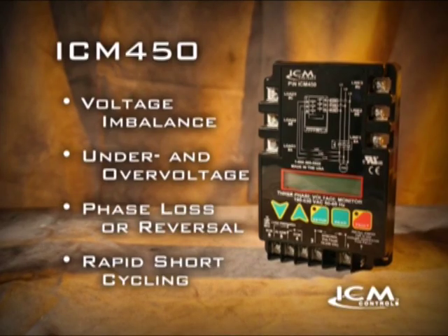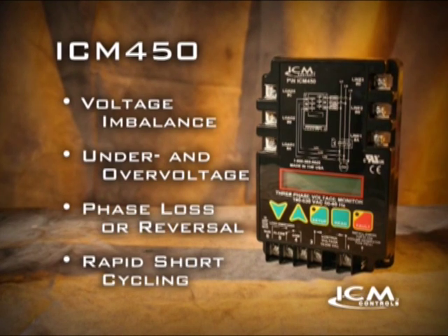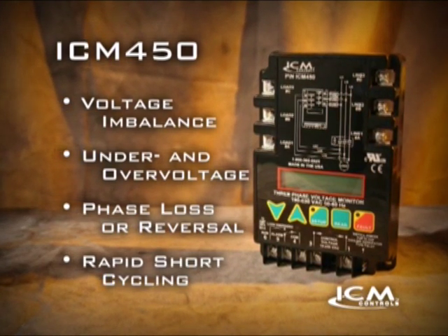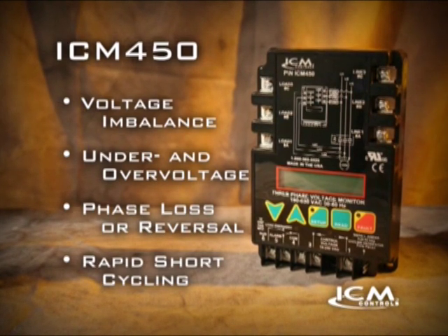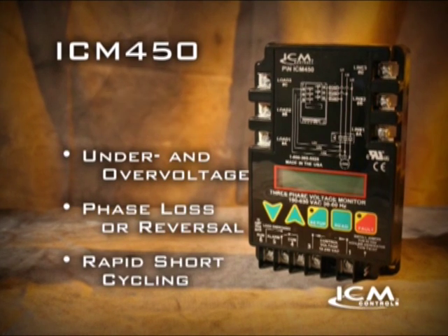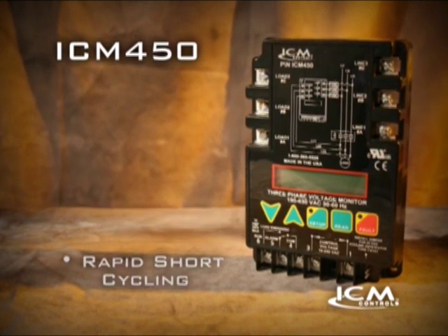Power problems are more common than most people think, and even a small problem can lead to premature compressor failure. The ICM 450 from ICM Controls provides advanced three-phase motor protection. It guards compressor motors and other three-phase loads from premature failure and damage caused by common voltage faults such as voltage imbalance, under and over voltage, phase loss or reversal, and rapid short cycling.